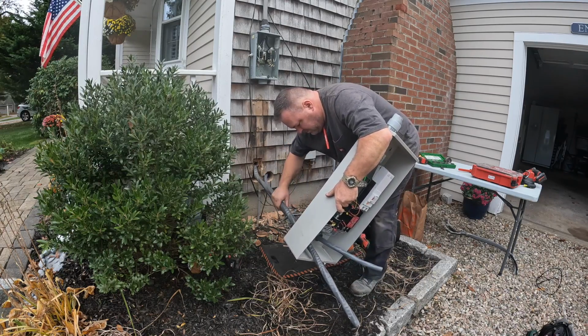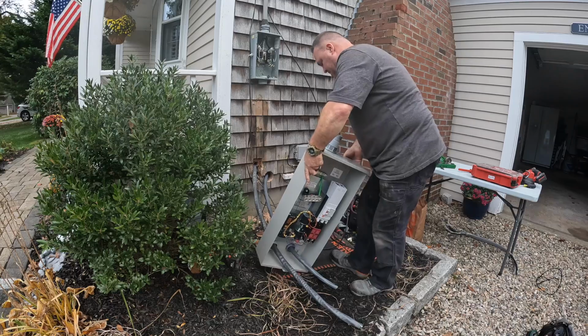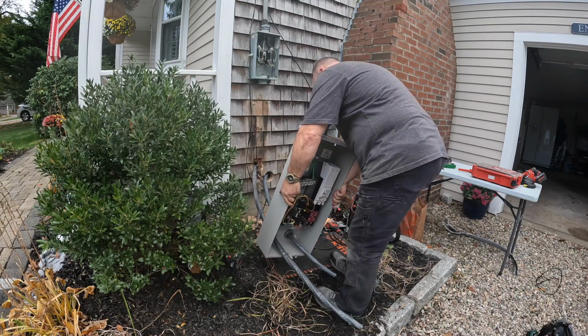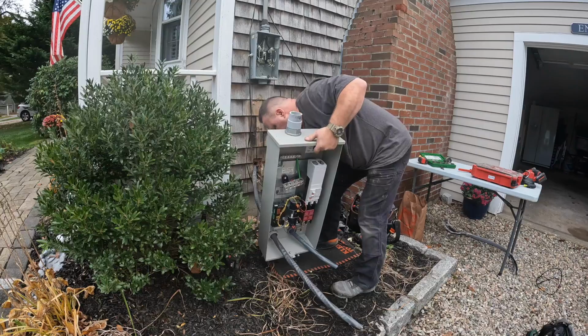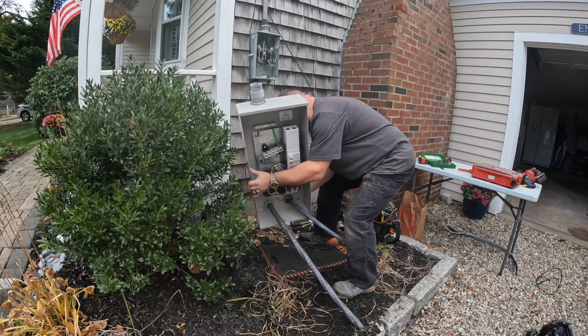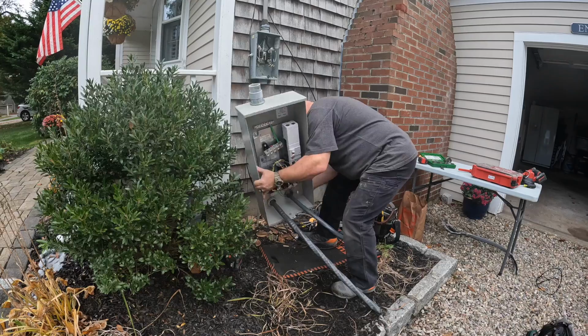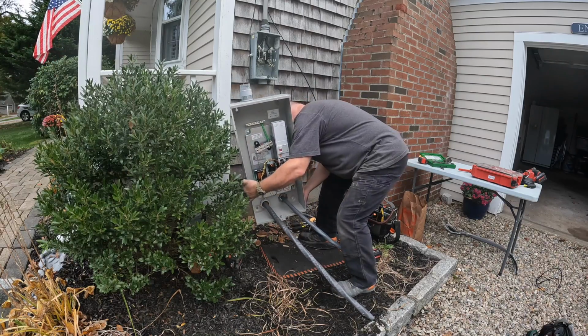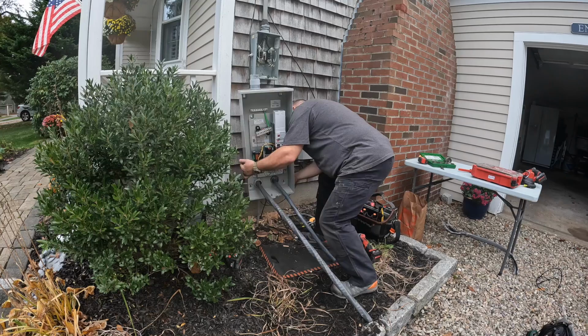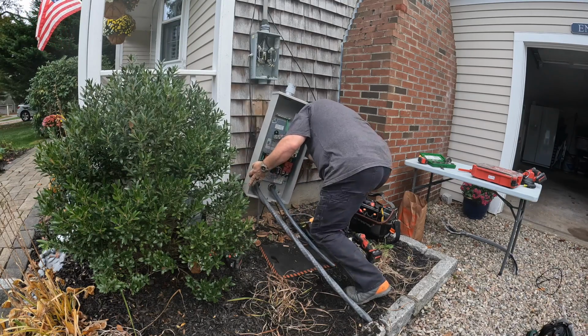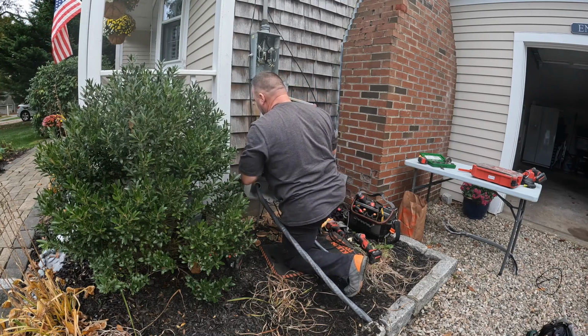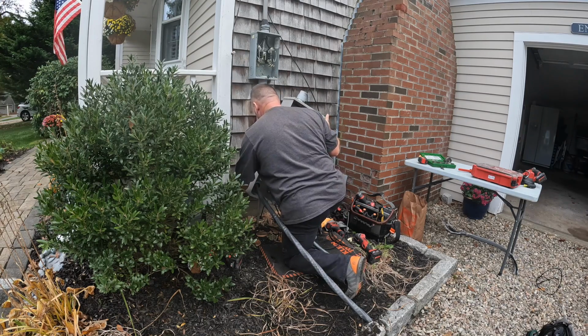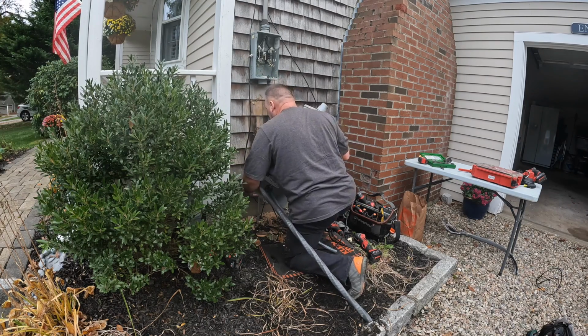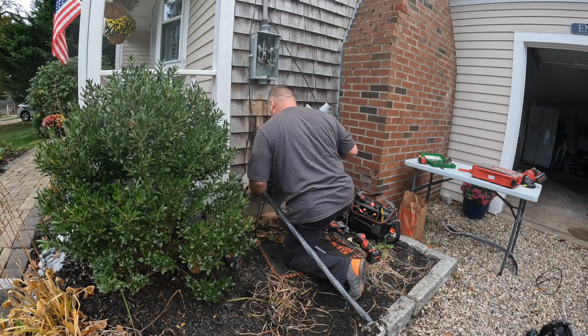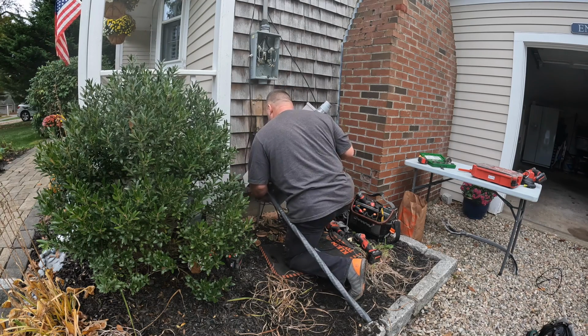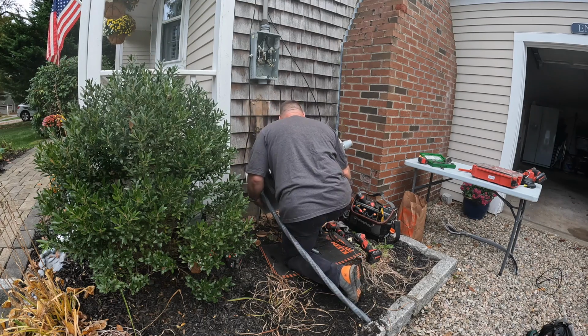The trick is to leave a little slack on these cables, then get the nipple on top to go into the male adapter coming out of the bottom of the meter. This isn't easy with these three different entry points to get it attached just right and secure, moving the cable and the exterior grounding block out of the way. Then you want to cover up where the old shingles are worn out or weathered, so it looks normal when done, which isn't always easy with this electrical work.